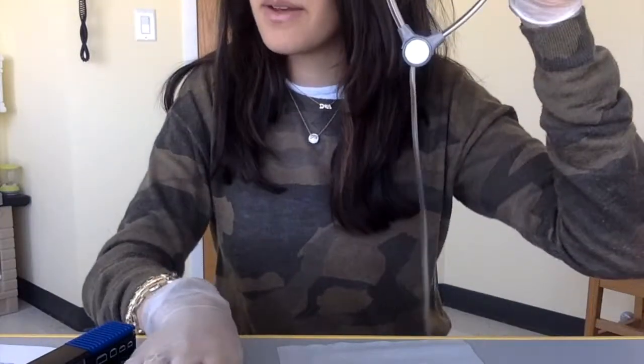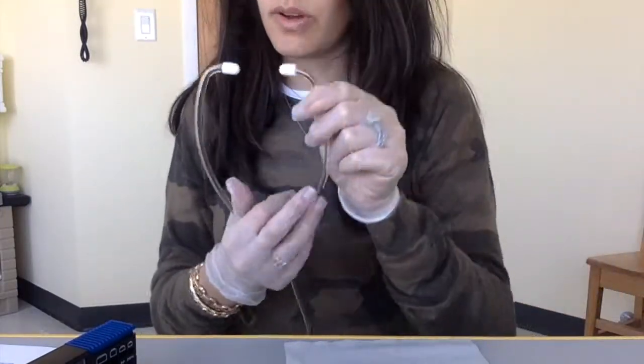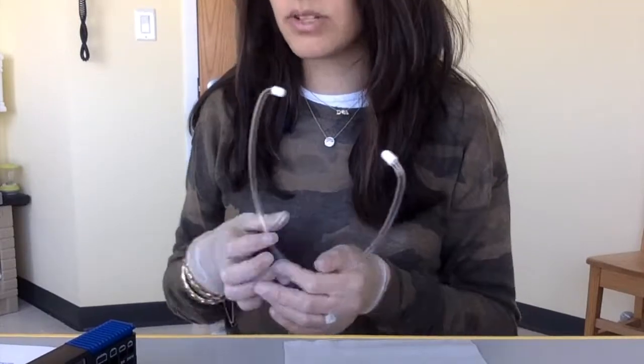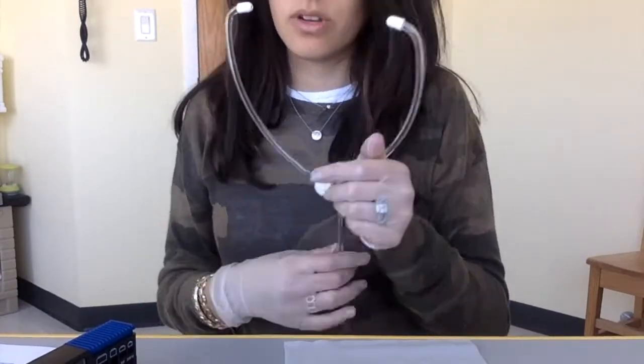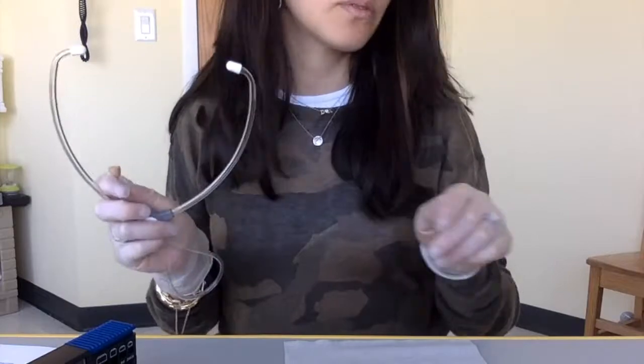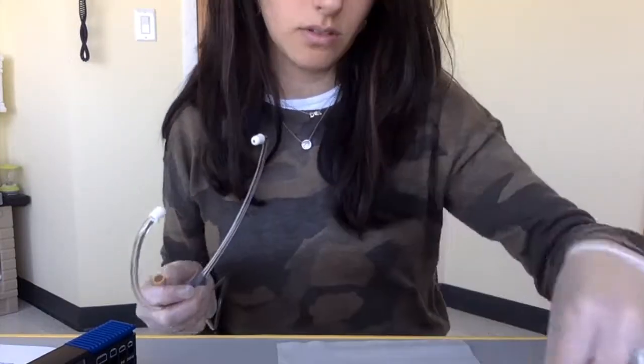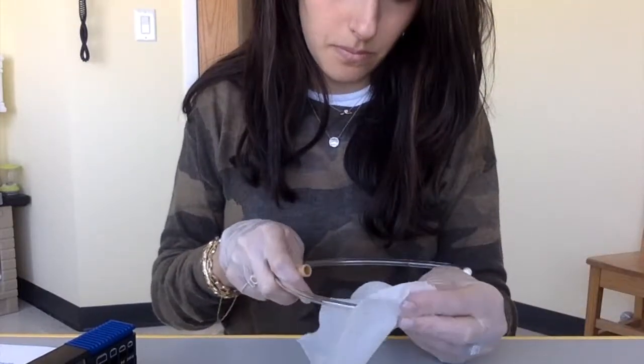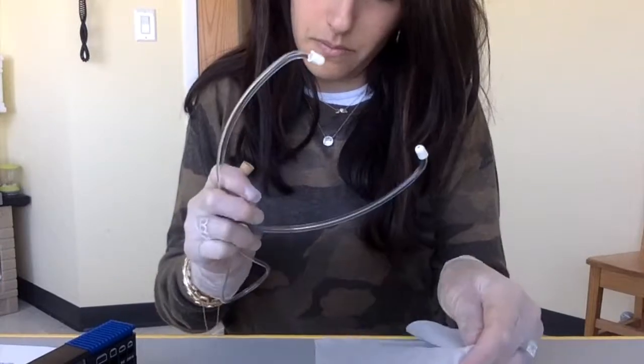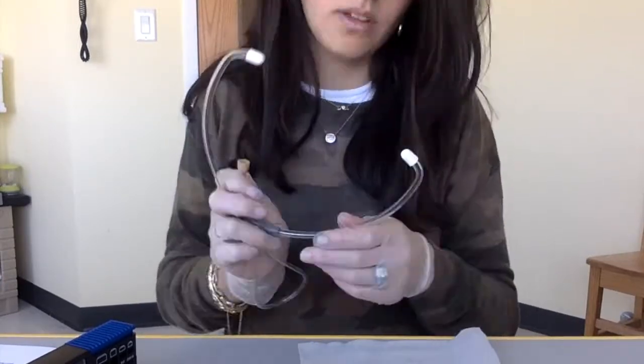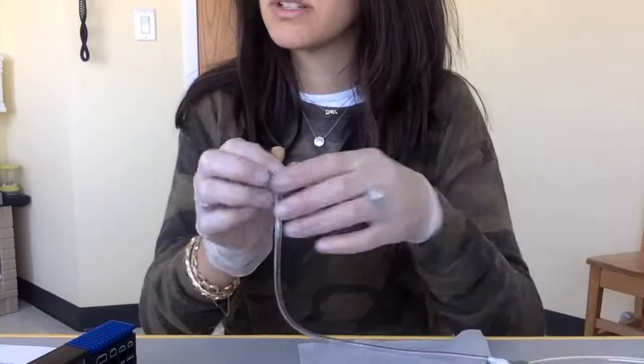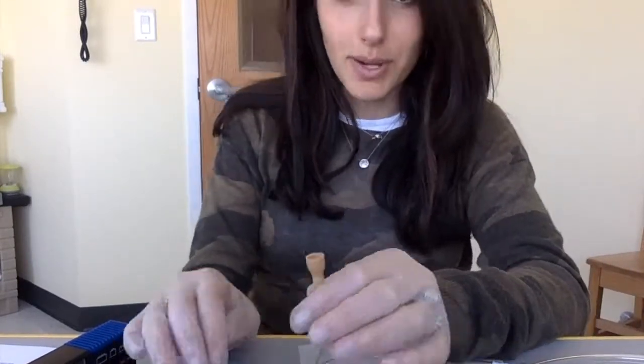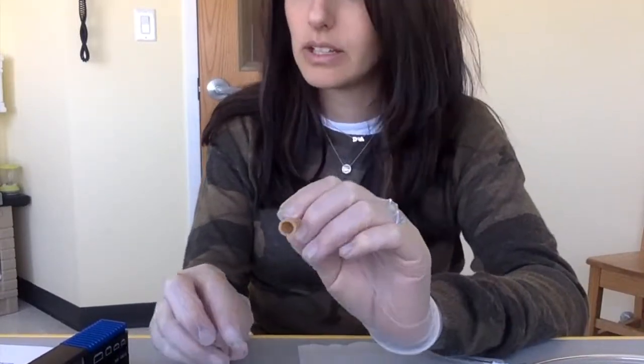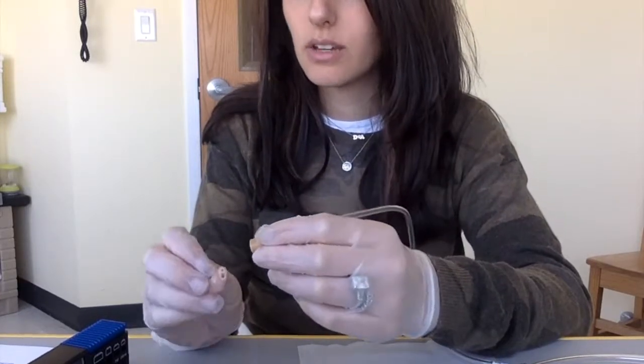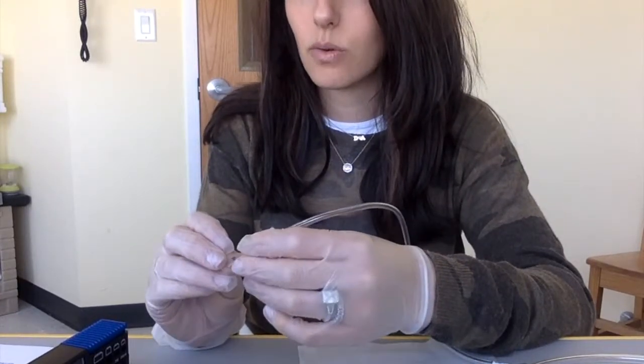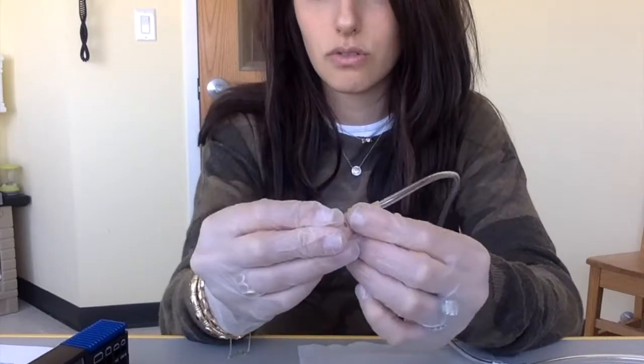Here we have our stethoscope. We don't have to listen to feedback because we know the battery is working. So, here's our stethoscope. I'm going to clean it before anything. Now we're going to perform a hearing check on the hearing aid to make sure it's working. I'm going to put the bell tip of the stethoscope over the sound bore as such.